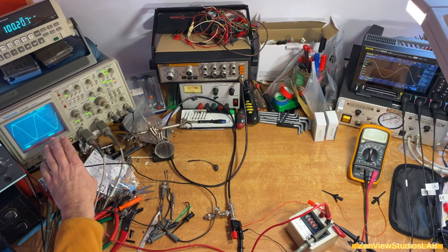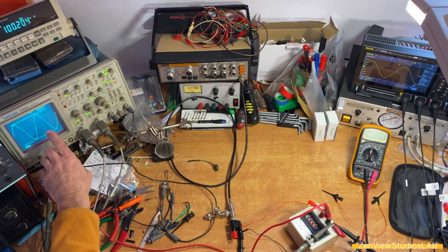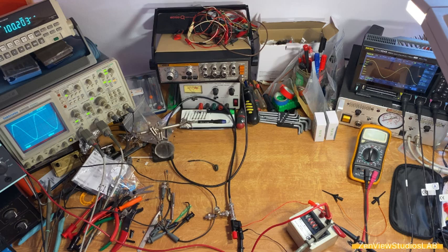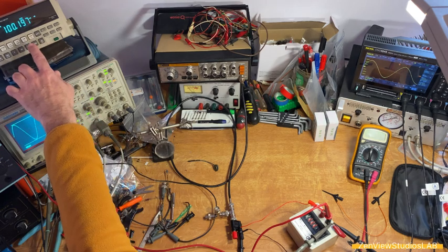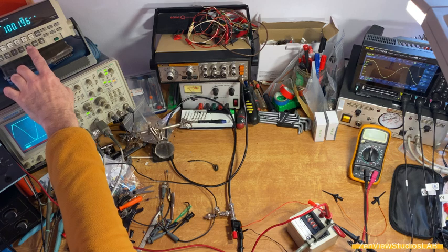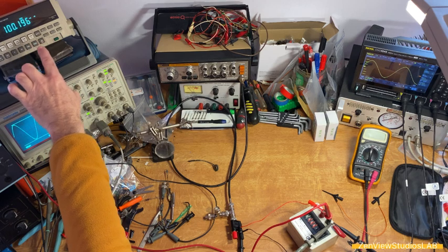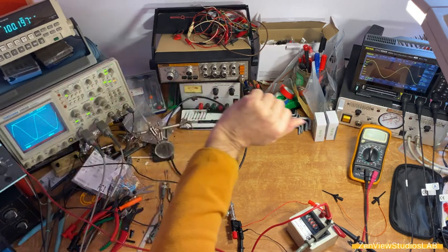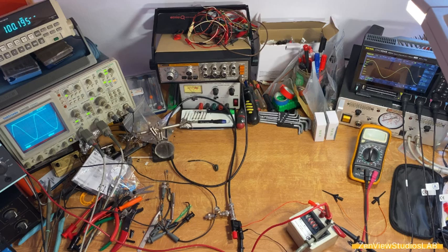We have, just as a check, the same signal displayed here. It's 300 millivolts peak to peak right here too. The scope and this scope, the digital and the analog, kind of agree. The analog says about 300 millivolts. More to the point is the Fluke, which says 100.197 millivolts or so RMS. That's really what we will base our measurement on. And this agrees too, because it shows also 100.2 millivolts RMS. That's the DVM from the scope, so the same measurement is displayed on both.